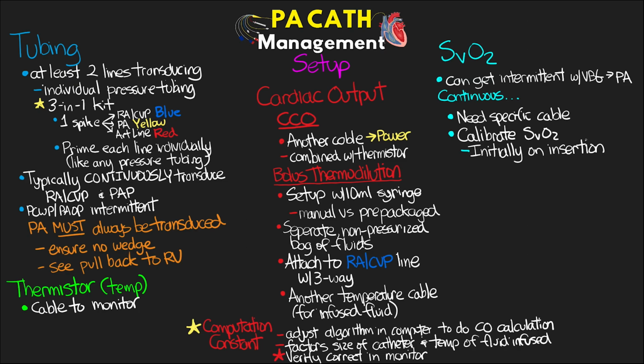We're going to select that, and basically it remembers the values that it records from the fiber optic line on the Swan at that moment in time. At that same time, we're also going to draw off of the PA port and run a VBG from there. The monitor holds itself in a standby position, remembering those last values. Once we have the VBG run and have the SVO2 value from that, we come back in, plug that number into the monitor, and it calibrates itself to that value.